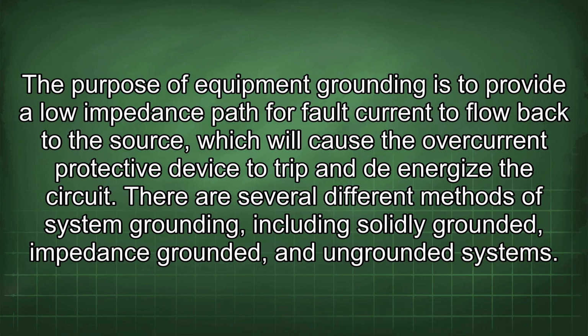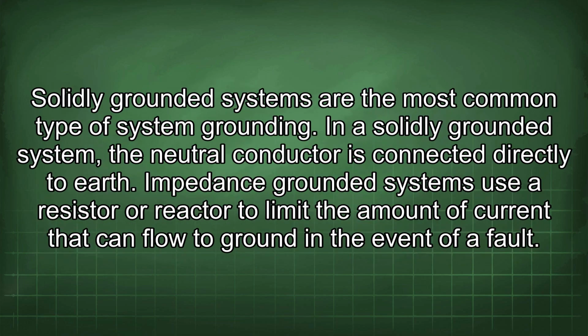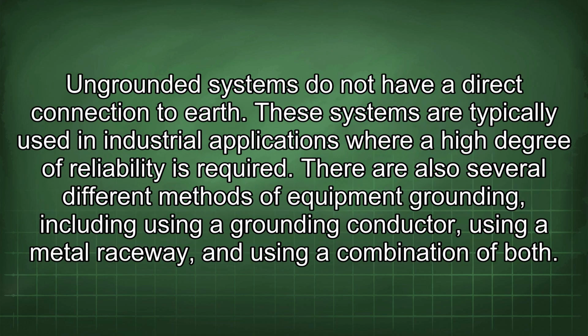There are several different methods of system grounding, including solidly grounded, impedance grounded, and ungrounded systems. Solidly grounded systems are the most common type of system grounding. In a solidly grounded system, the neutral conductor is connected directly to earth. Impedance grounded systems use a resistor or reactor to limit the amount of current that can flow to ground in the event of a fault. Ungrounded systems do not have a direct connection to earth. These systems are typically used in industrial applications where a high degree of reliability is required.